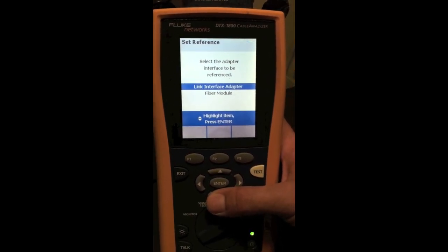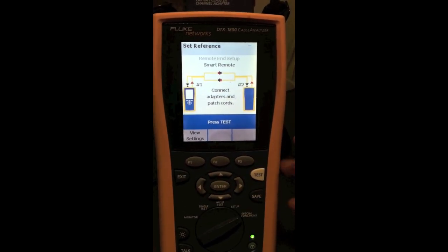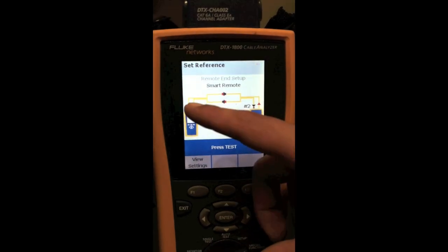So next thing we want to do is go swap over one more time to special functions and we're going to set our reference. And here you will see different settings for link interface adapter which we're not using and our fiber module which we are. Hit enter and it will give you a diagram on how to set up. You have your input going over into your input on the other side and your output again going to your output on the other side. So now we're going to take these cables and couple them together and establish a link.